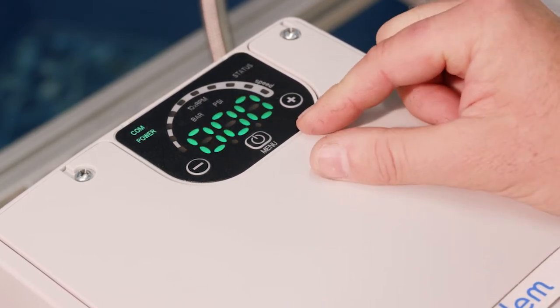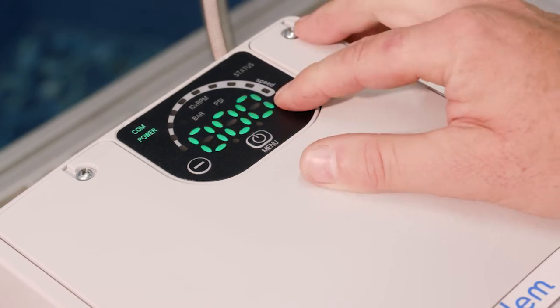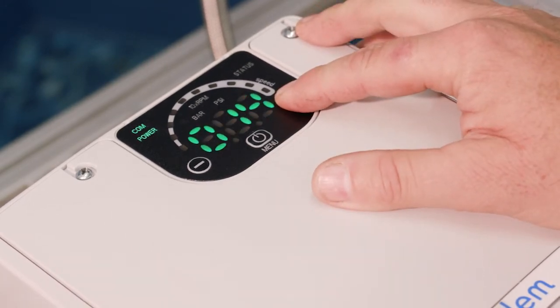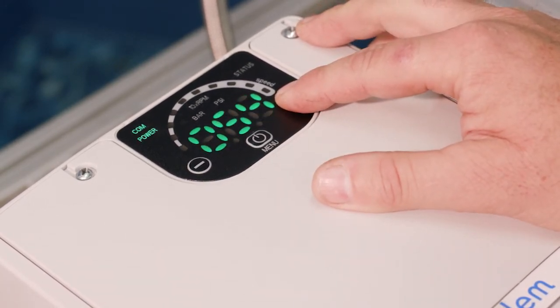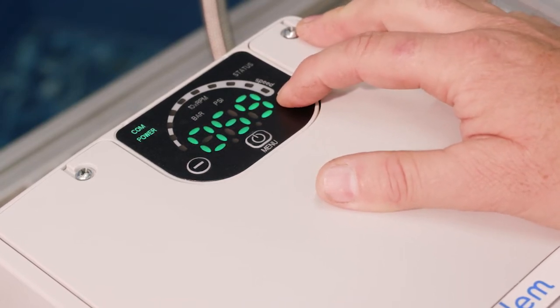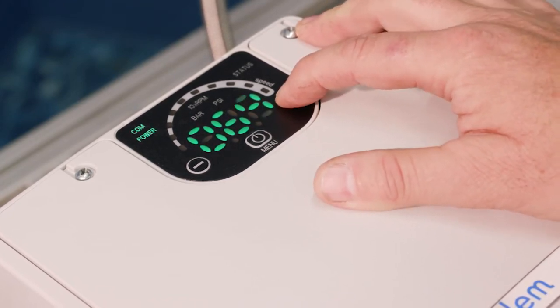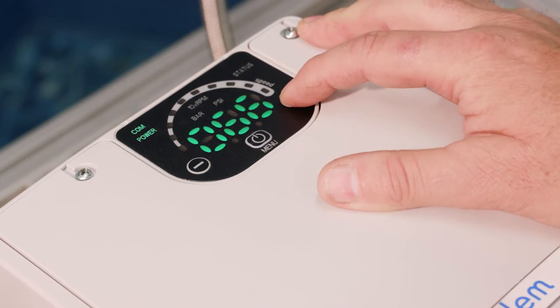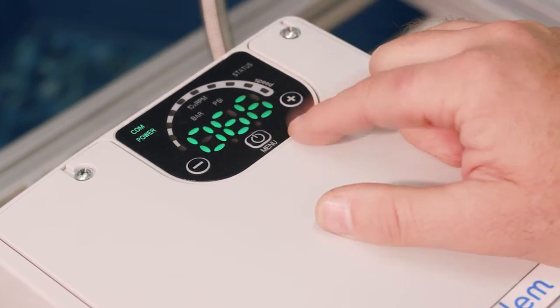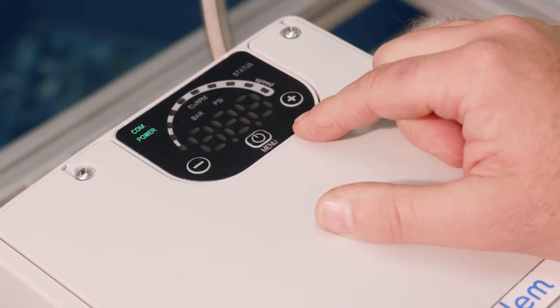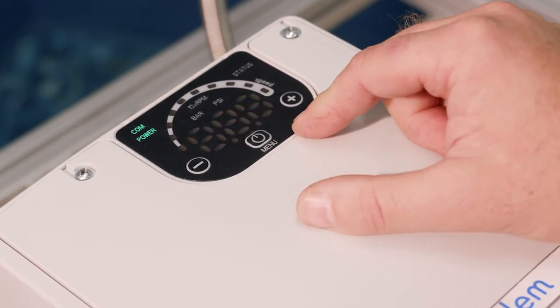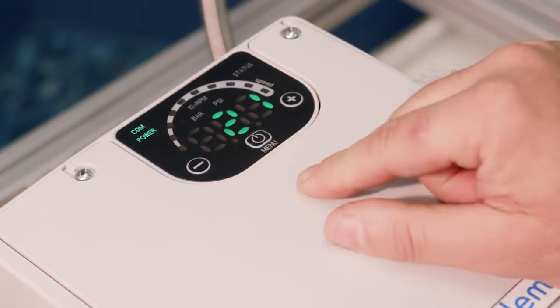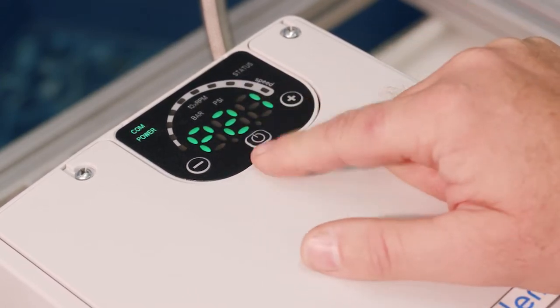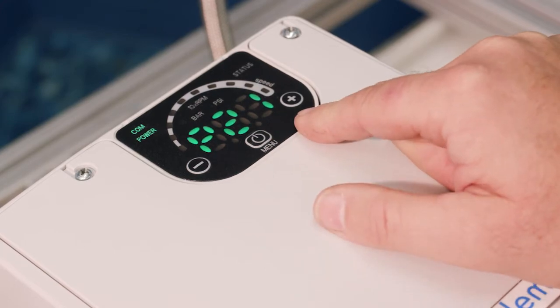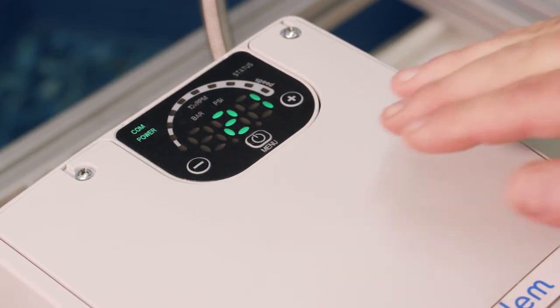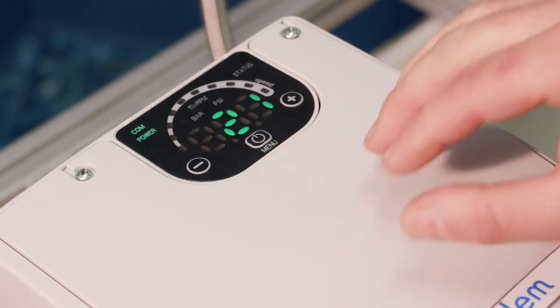So we have to put the standard default password in, which is 66, and that will allow us to get to parameter P21 and above. If you do not do this, it will not let you get past those other parameters, past 20. So you put the password in there, and you can see that it takes you to 21. And again, we're just going to go to the bare minimum for a duplex.